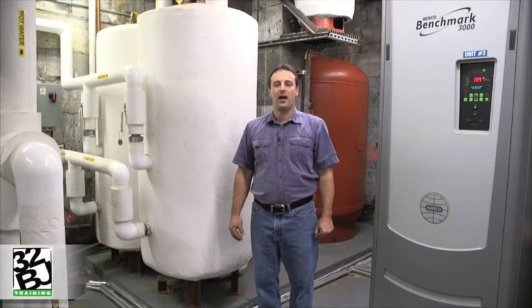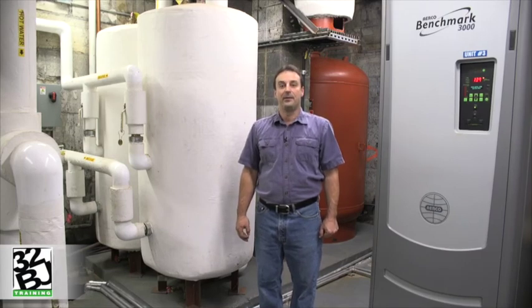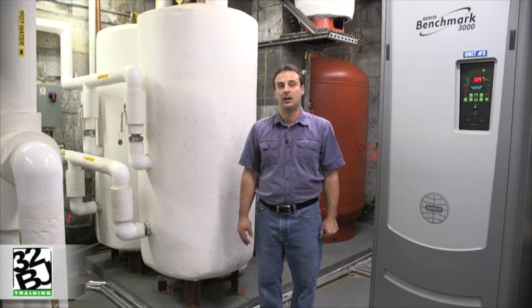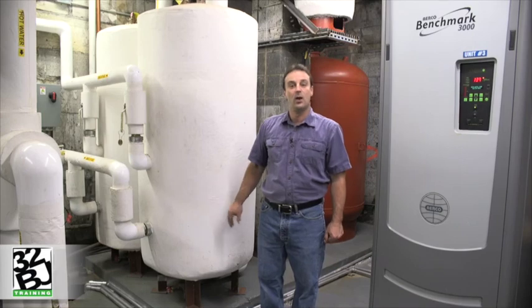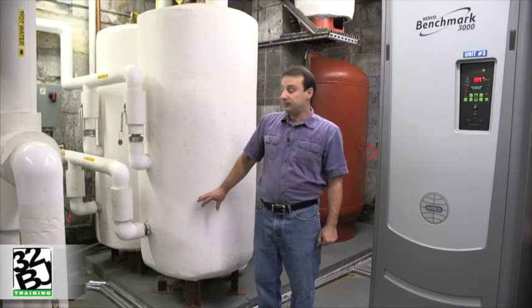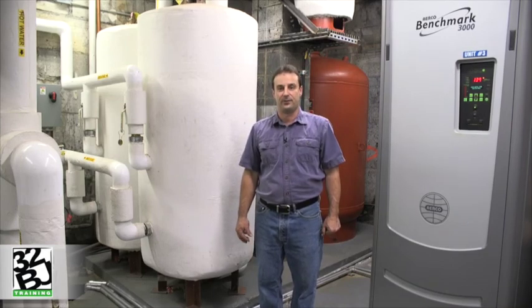Due to the small volume of water contained in the plate frame heat exchanger and the large heating demand for domestic hot water in this 33-story multifamily residential building, 2 large storage tanks will be required in order to meet that demand. These 2 storage tanks are heavily insulated to prevent the jacket losses that we've seen with other types of systems.